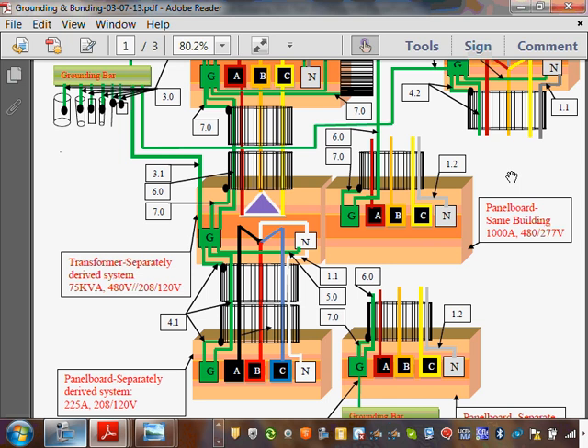So with an EMT conduit, typically we have a flex to tie to it, so you have to pull an equipment grounding conductor, tie the jump over the flex from the EMT with a bushing directly to the enclosure. You have to have a good, solid mechanical connection between whatever metallic conduit you have and the frame of the transformer. That could be a conductor, or if you're tying your rigid or EMT directly to the transformer, which we wouldn't do unless you're coming from the bottom, then that bushing could do it, but most likely it would be a bonding bushing right in here with your equipment grounding conductor.